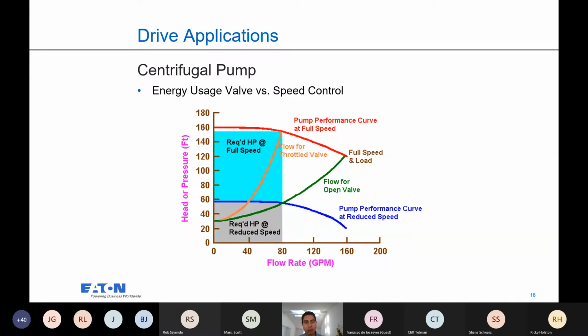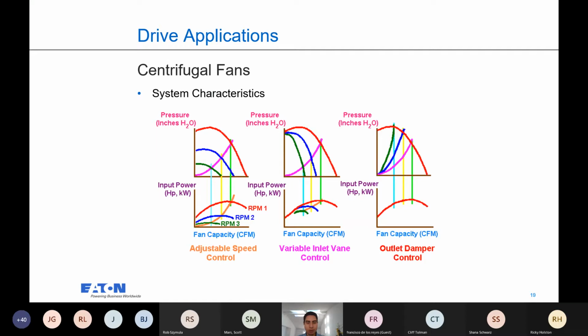So here are the 2 graphs for comparison. Obviously, there's a big difference here. You used a different pump curve to achieve this, and all that extra head that was not used is the energy savings. So here's a few different examples. Obviously, anytime you're using a valve or vane, you go into the higher head curves, and then with adjustable flow is the most efficient operation here.